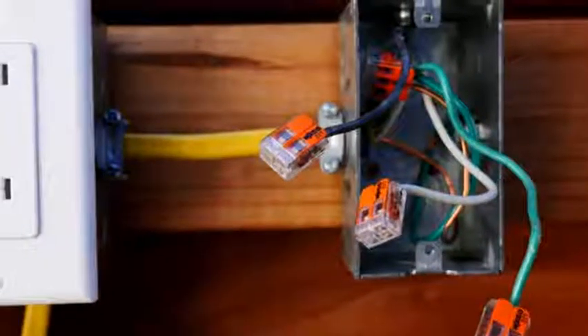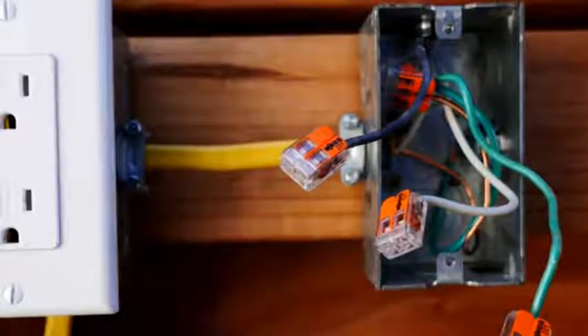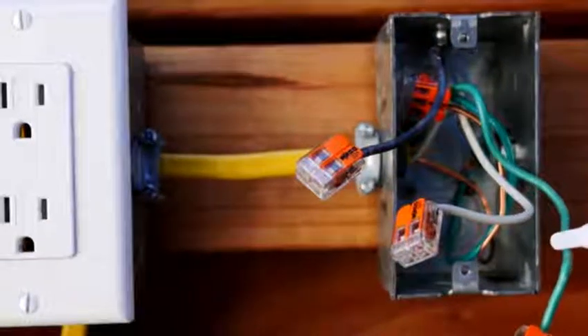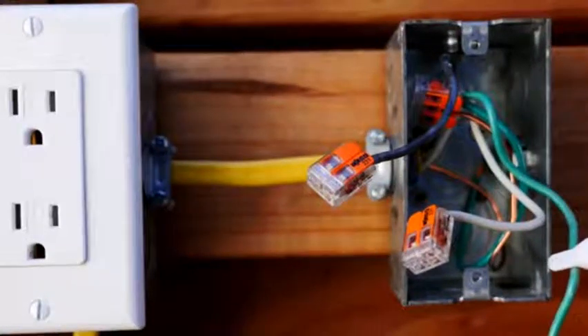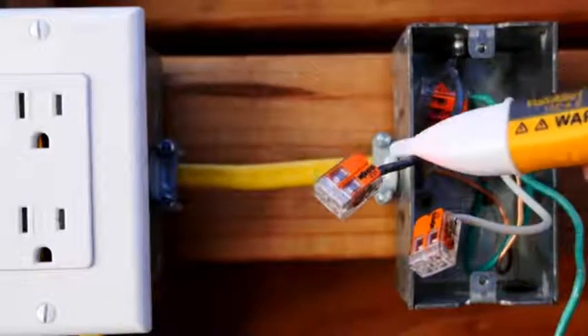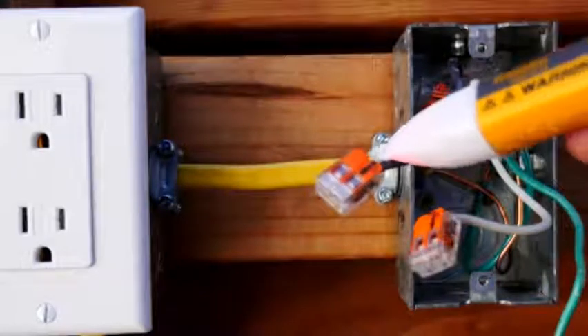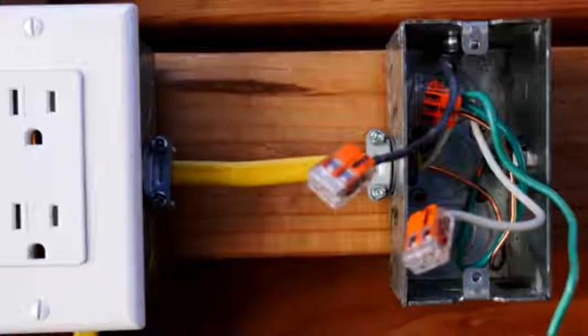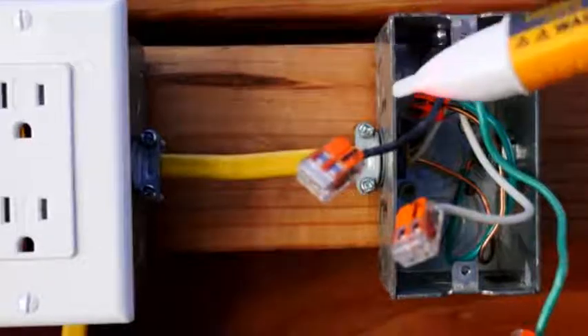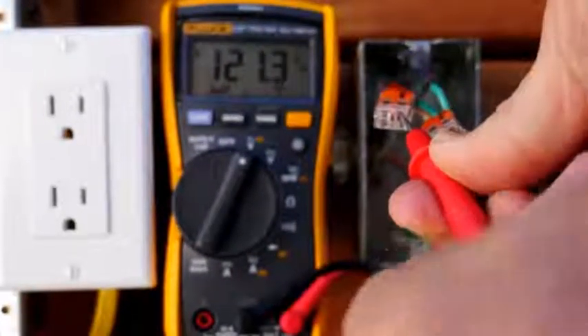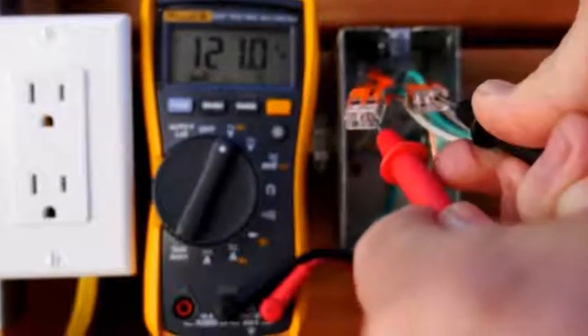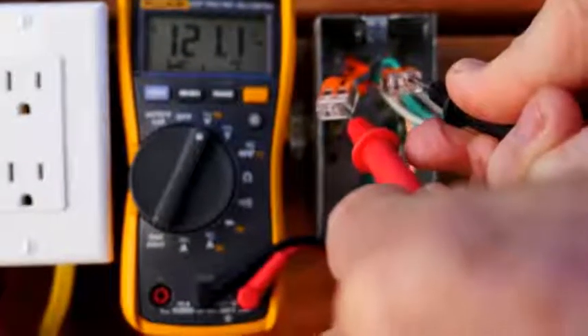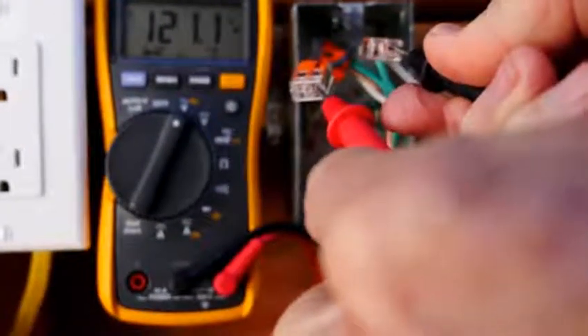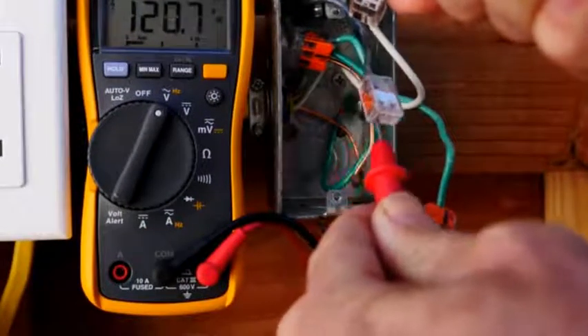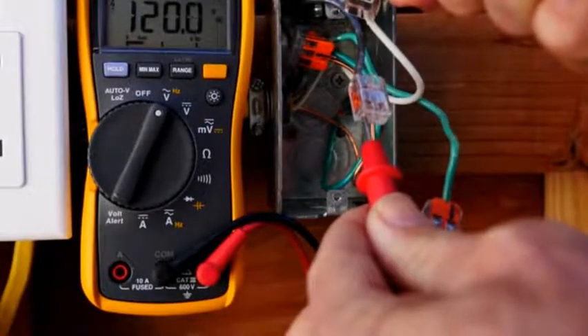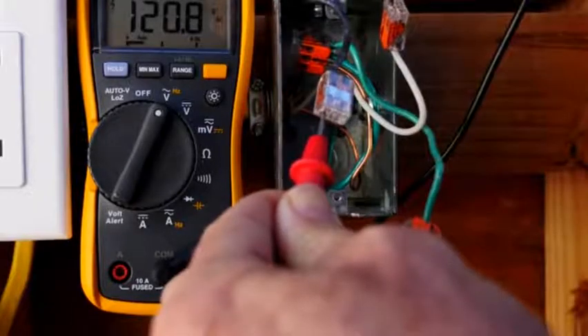I have temporarily turned back on the circuit breaker. I put the Wago lever nuts on all of the wires for safety, and I'm using my voltage detector. I'll test all the wires, and this is your hot wire right here. So the black is the hot. Whenever you're working on a receptacle, it's always a good idea to test and see what kind of voltage you're getting. And here I'm reading 121 volts AC, and I'm using my leads in the ports of the Wago lever nuts. That's a good, safe way to do it.